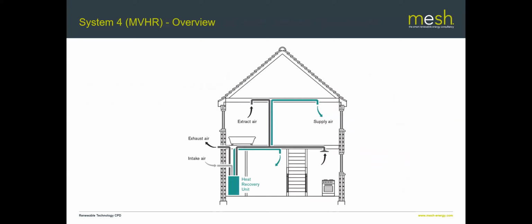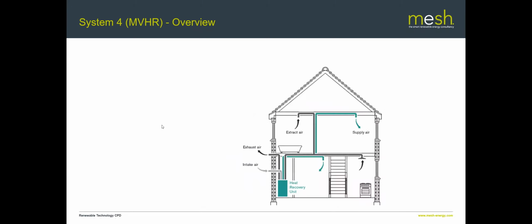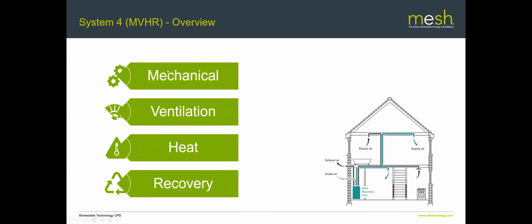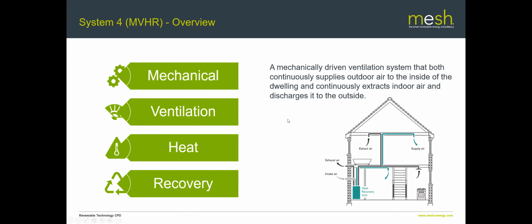And finally, we have MVHR, and this is what the majority of today's talk is about. MVHR is the king of ventilation systems as far as domestic goes. What you're doing is mechanically supplying and extracting air from the property. And in the middle, you have a heat recovery unit, because your extract air is air that you've paid to warm up in the house, and you're taking that back to the heat recovery unit. You're stripping the heat out of it, and you're exhausting the air to the outside. MVHR stands for mechanical ventilation with heat recovery. The heat recovery part we'll talk about in a second. Mechanical ventilation is both for supplying air and for extracting air, and that's the definition given in ADF.